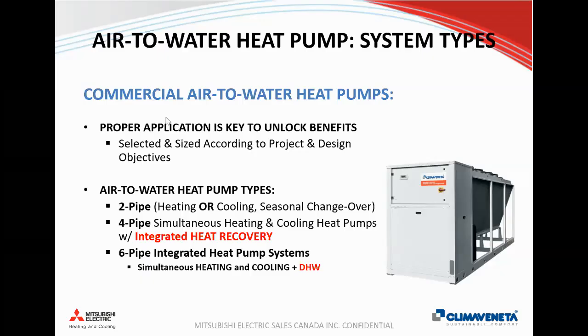You'll get the best benefit from the heat pump if you design it alongside with the building and selecting your heat emitters for the building to get the best balance between all the parameters that designers are trying to balance for their clients, like first cost, maintenance, efficiency, and operating costs, and so on. But just really quickly, we'll talk about air to water heat pumps. So everything I've talked about applies to either 2-pipe, 4-pipe, or 6-pipe air to water heat pump systems. Obviously, commercial buildings operate with heating or cooling year round.